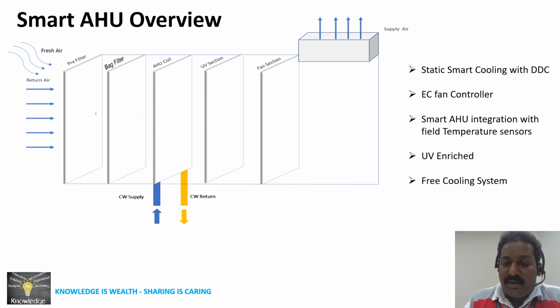And the last is the free cooling system. Nowadays, through a heat exchanger, a small portion of free cooling is utilized, but there is always scope for improving to 100% free cooling, pumping 100% ambient air to the field area if parameters and temperature are matched. Because we know that in urban areas the air is more polluted, we can't directly use ambient air as it is in the field workstation area.